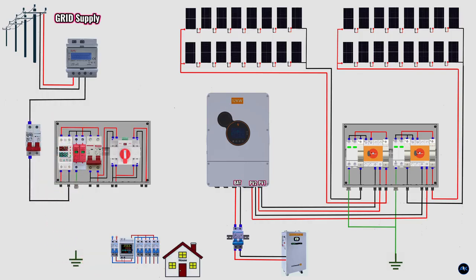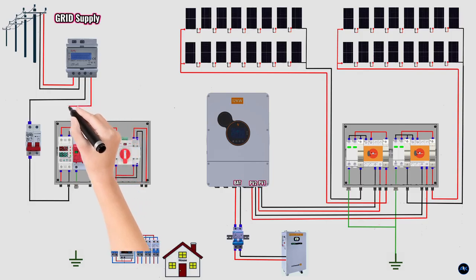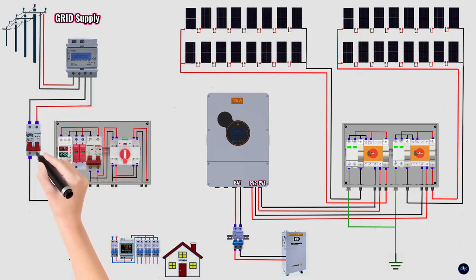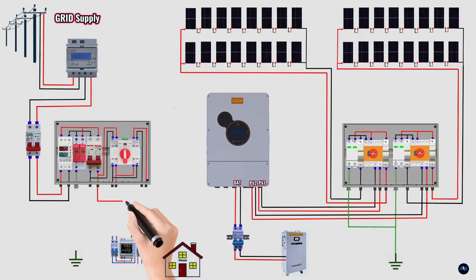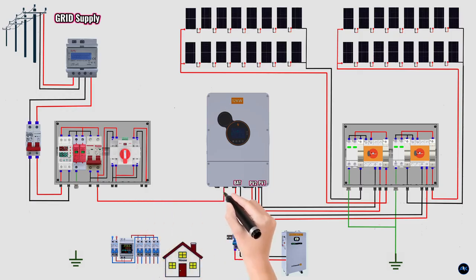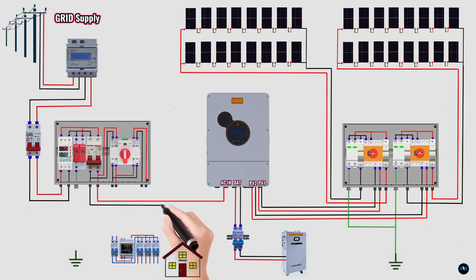This meter measures how much electricity is imported from the grid and how much is exported back. From the meter, the AC power passes through an AC isolator switch. This allows the inverter to be safely disconnected from the grid. After the AC isolator, the power flows through an undervoltage and overvoltage protection relay. If the grid voltage becomes too high or too low, this relay disconnects the inverter automatically. Next, the AC cables pass through an AC surge protection device. This protects the inverter and household equipment from grid-side voltage surges.